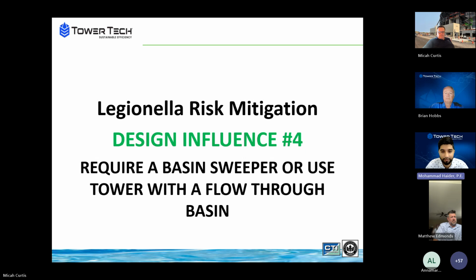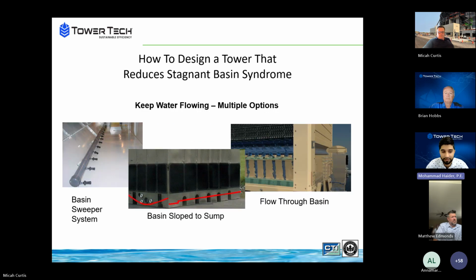Yeah, so this item right here, design influence number 4, we're talking about basin sweeping systems. So in a standard conventional tower, you have a basin where the water gets stagnant. So one of the solutions that you get for those type of towers, which I've actually employed myself, are basin sweeping systems. And the interesting thing about that is that they essentially cause that basin to have an additional velocity of water that is designed to start stopping those stagnant zones of water. So it's better than nothing to have a basin sweeping system, but what you really want to have is a high velocity flow through basin or some sloped system to where that water has a natural high velocity.